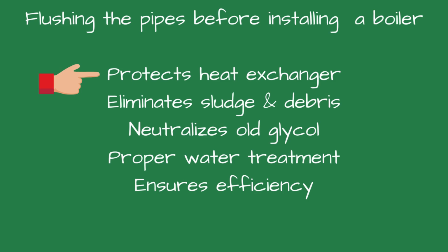So what are the benefits of flushing the piping prior to installing a new boiler? Number 1, it protects the heat exchanger. Clean, neutral water ensures proper flow and prevents localized overheating or scaling that can crack, warp, or foul the heat exchanger. Number 2, it eliminates sludge and debris. Removing abrasive particles reduces wear on pumps, valves, and sensors, extending the life of every component in the system. Number 3, it neutralizes the old glycol. When glycol ages, it breaks down into organic acids. These acids lower pH, corrode steel, pit copper, and eat away at aluminum heat exchangers. Flushing eliminates these corrosive byproducts.